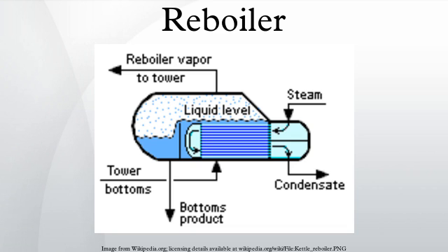Forced Circulation Reboilers: A forced circulation reboiler uses a pump to circulate the column bottom's liquid through the reboiler. This is useful if the reboiler must be located far from the column, or if the bottoms product is extremely viscous. Some fluids are temperature sensitive, such as those subject to polymerization by contact with high-temperature heat transfer tube walls. High liquid recirculation rates are used to reduce tube wall temperatures, thereby reducing polymerization on the tube and associated fouling.